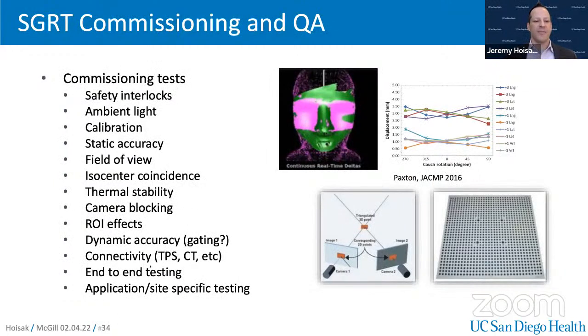And ultimately, any commissioning should end with end-to-end testing, where we test the entire workflow, from imaging a patient, setting them up on the table, delivering a treatment, and then monitoring treatment throughout using SGRT. And then there may be application or site-specific testing, such as if we have to add an in-bore system.